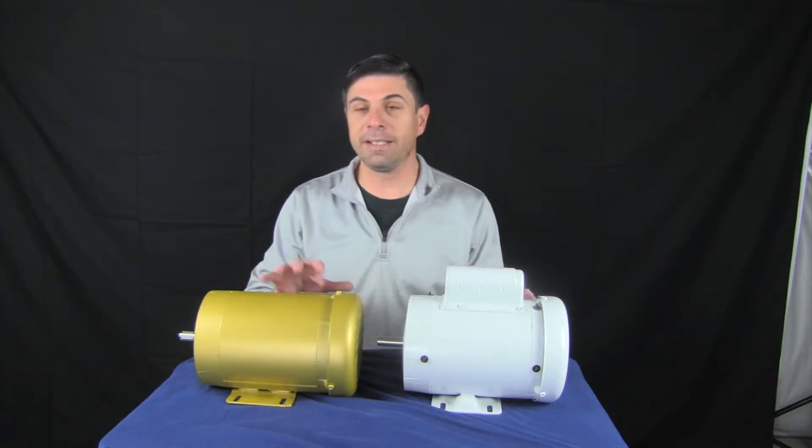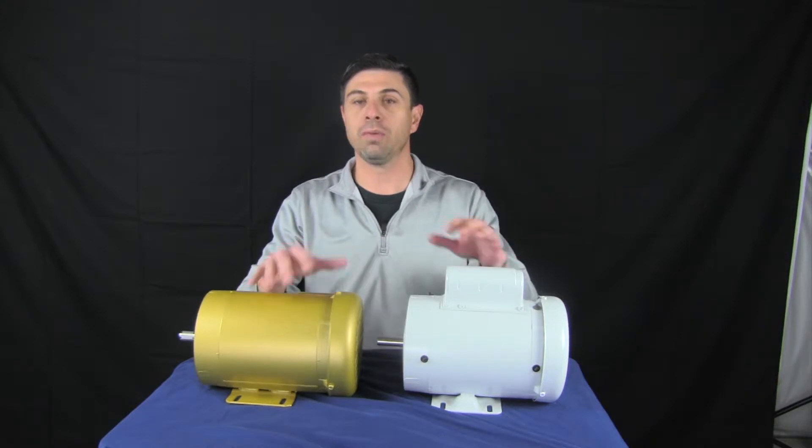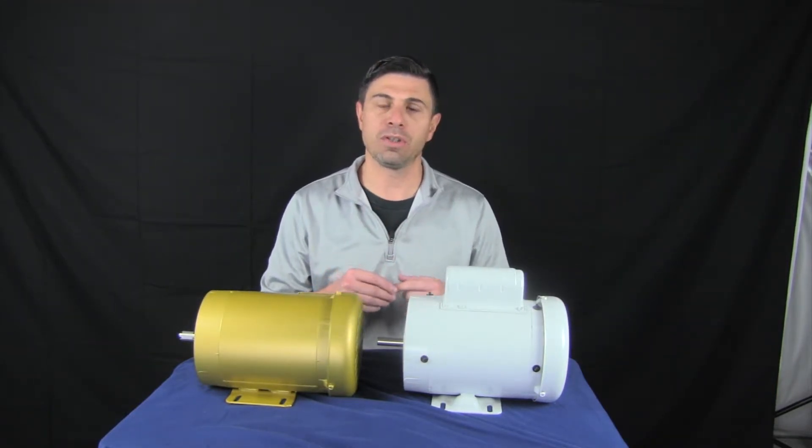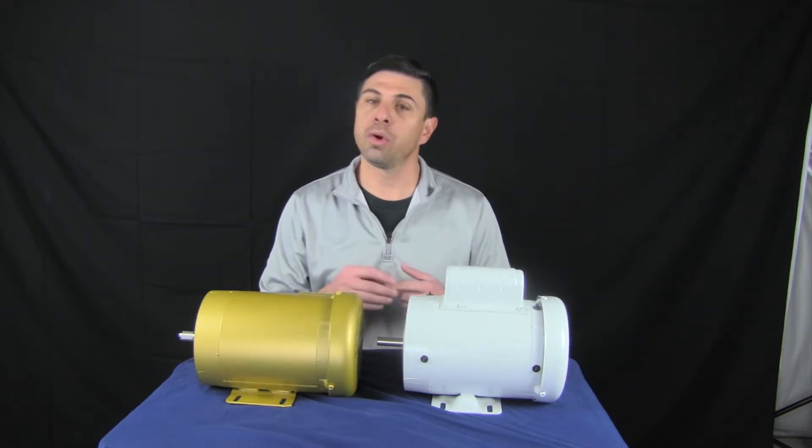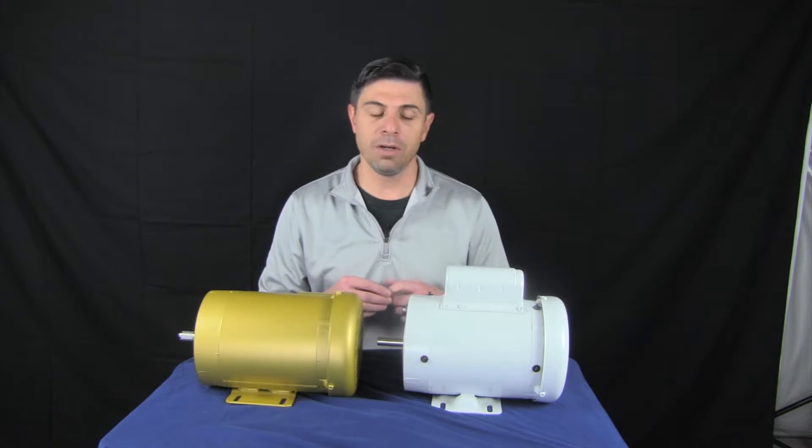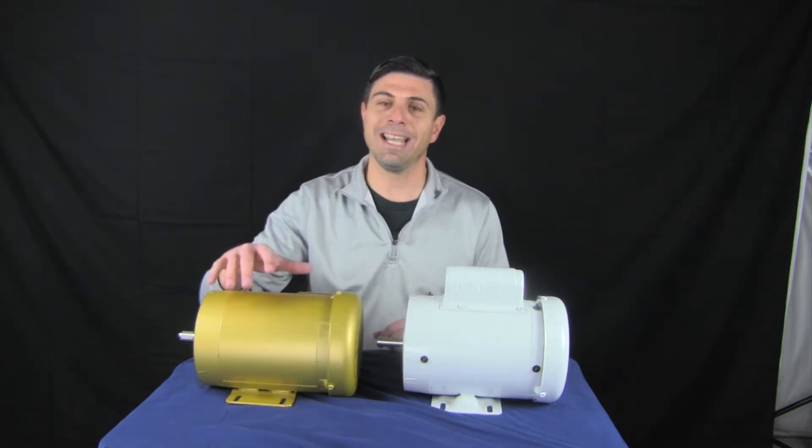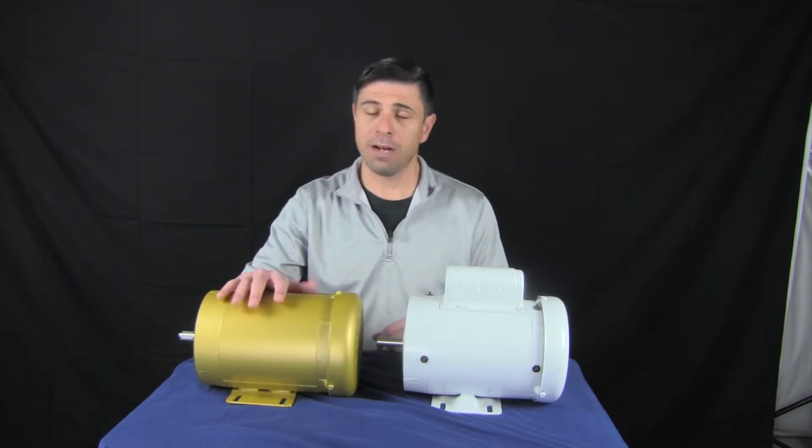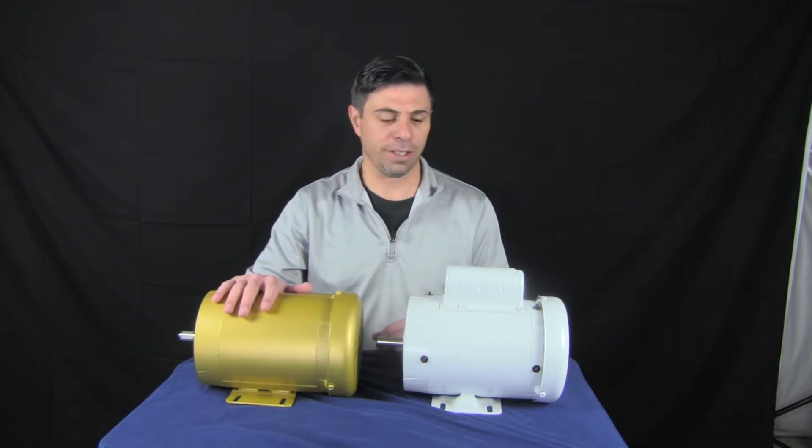And really the basic differences between these motors and your more popular industrial motors like the ODP, which is open drip proof motor, and your TENV motor, which is totally enclosed non-ventilated motor. The ODP is gonna have vents along the enclosure, so it's an open enclosure, so debris can get inside the motor, and that'll be a quick way for you to identify that type of motor in your facility.